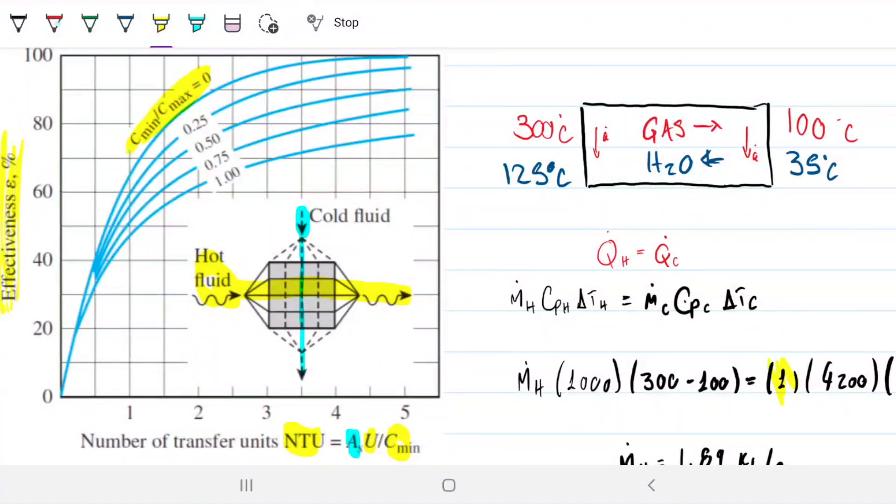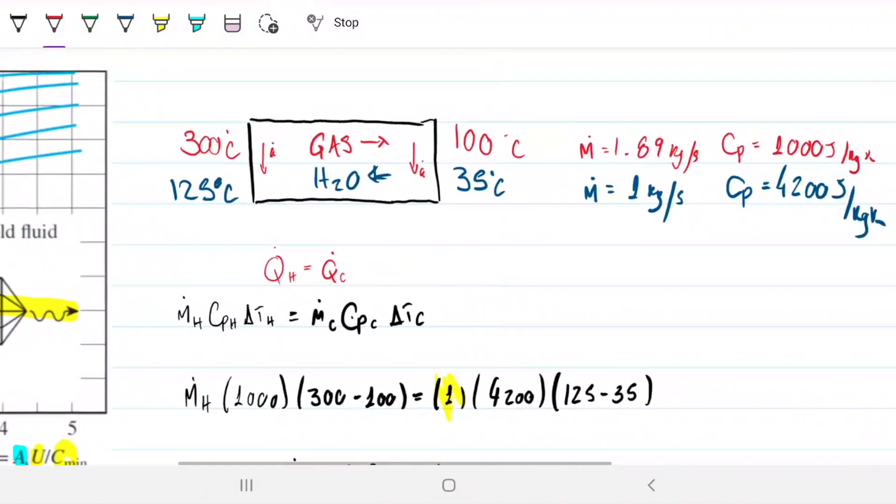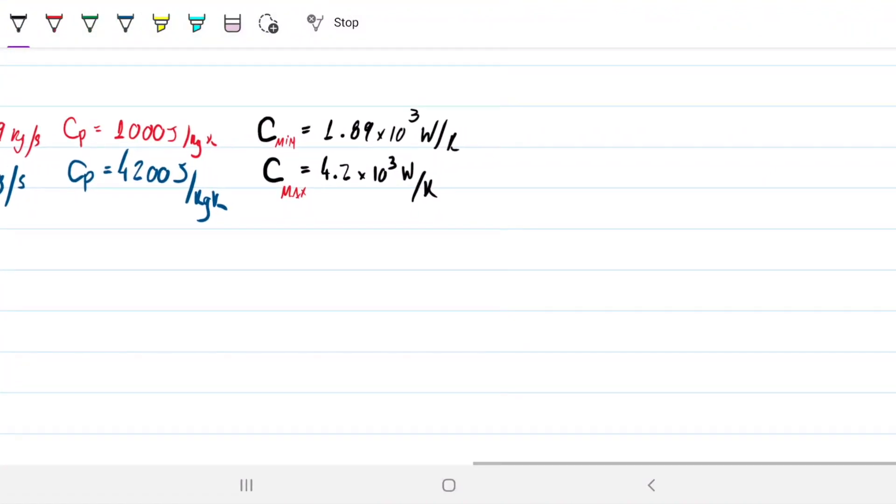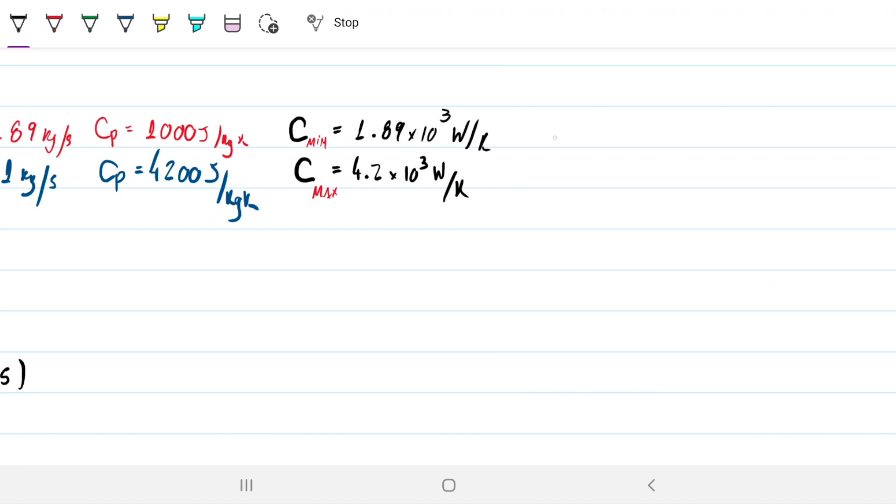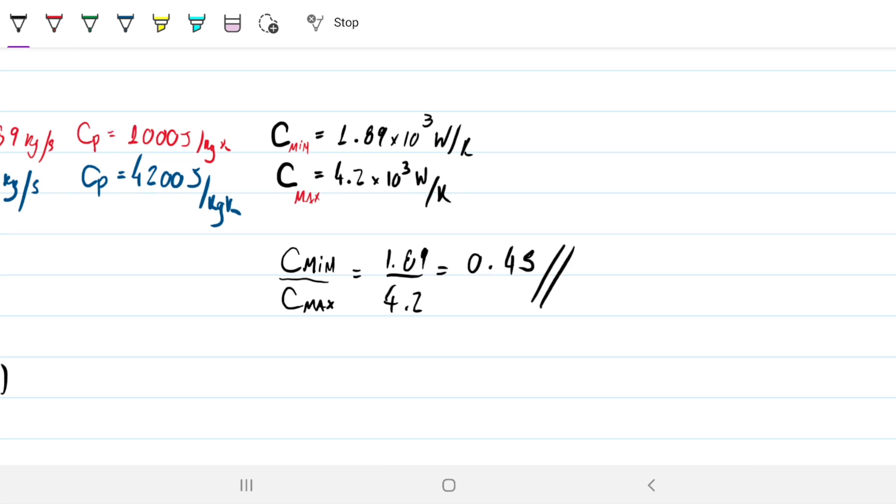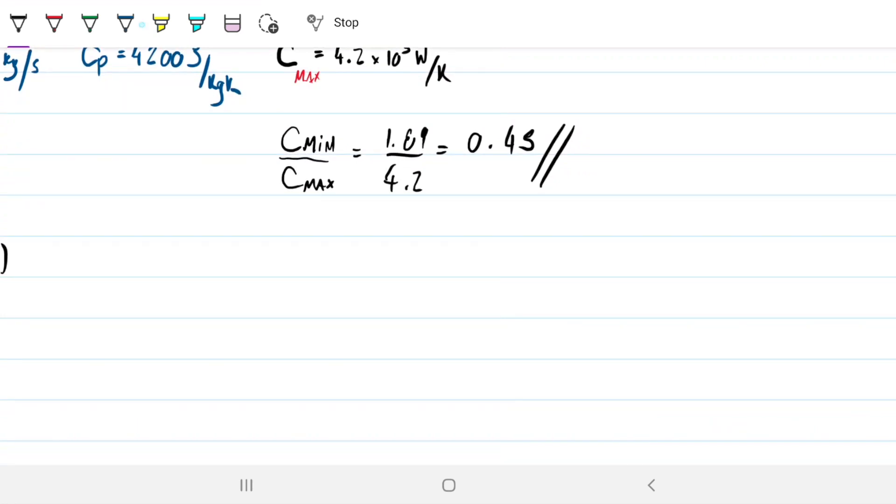This is straightforward for us to grab. We have both of them, just divide them up, find the ratio. The effectiveness is what we're missing next. So let's just start by doing the ratio between these two fellows. So that will be C min divided by C max, which is just 1.89 divided by 4.2. There is no unit. Units are the same, so this is 0.45. So that's one of the things we need to find the NTU.